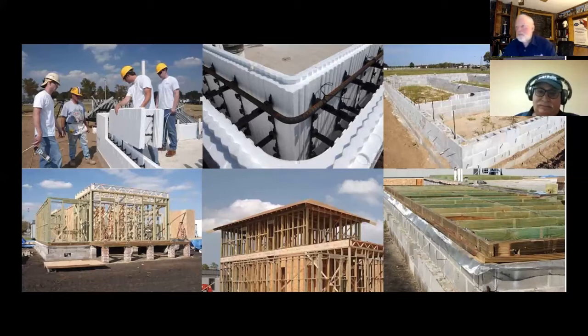So we have various configurations here. One of the things we show at LaHouse is four ways to keep your ductwork within the conditioned space, within that thermal boundary of insulation and air barrier. One way is the unvented semi-conditioned attic, which we also use as an additional exhibit room where we show lots of things. It's an unvented attic where the insulation is spray foam at the roof line instead of the attic floor.